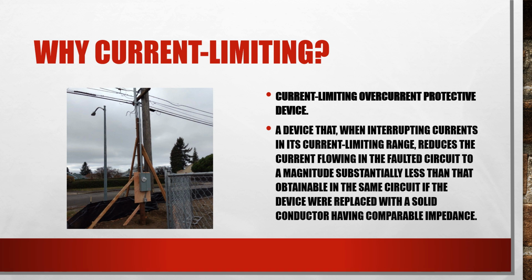Why current limiting? Well, if you look at the picture that we see here, our temporary pole is often, just by nature, very close to the utility company's transformer. What that means is the available fault current at our equipment may be much higher than at other installations, where we would run long distances through our service conductors to get there. Right here, we're real close. This means that there's nothing really limiting that amount of current that comes from the utility transformer. So to have this in place is going to, again, cut down on the damage that we see to our equipment in this 277/480 volt system.